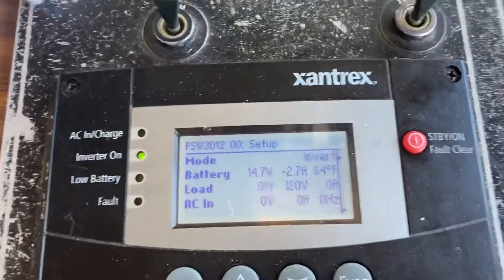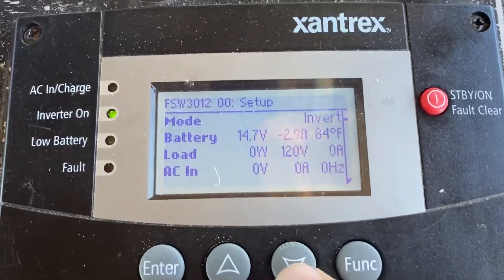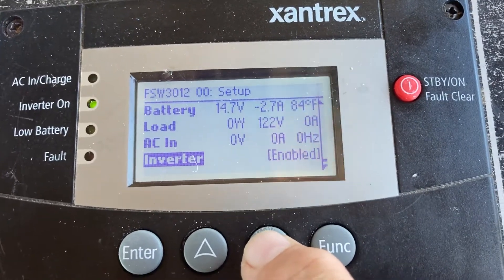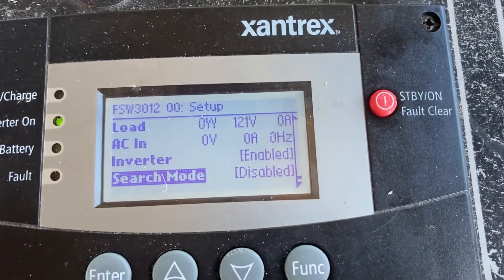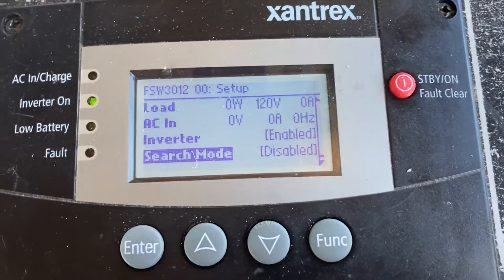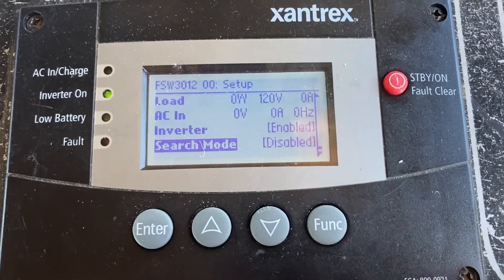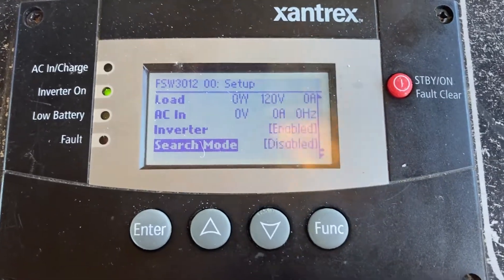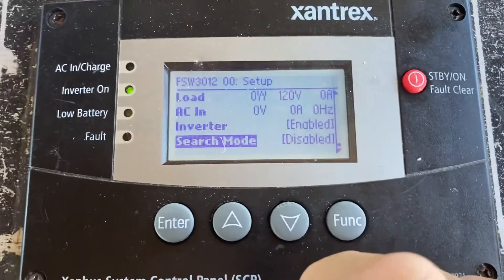You see this nice little setup here. What's causing the problem is not on this screen, but it is on the screen — it's just off the screen. You see inverter is highlighted enabled — that's what you want. This is the problem: Search mode — it's got to be disabled. We don't need that search feature at all. Somehow that gets changed and we have the problem. So make sure that's correct and then everything works lovely.